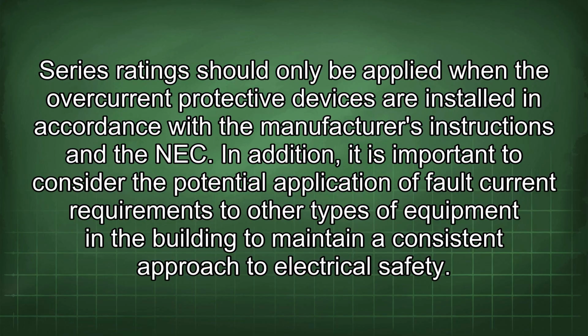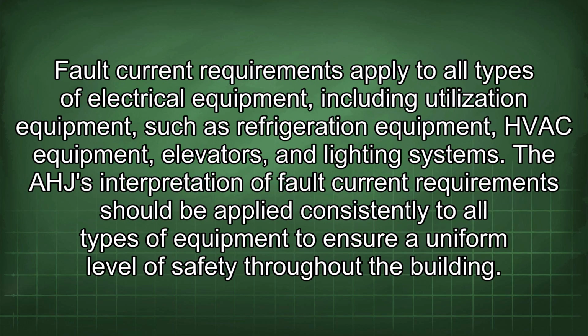Series ratings should only be applied when the overcurrent protective devices are installed in accordance with the manufacturer's instructions and the NEC. In addition, it is important to consider the potential application of fault current requirements to other types of equipment in the building to maintain a consistent approach to electrical safety. Fault current requirements apply to all types of electrical equipment, including utilization equipment such as refrigeration equipment, HVAC equipment, elevators, and lighting systems. The AHJ interpretation of fault current requirements should be applied consistently to all types of equipment to ensure a uniform level of safety throughout the building.